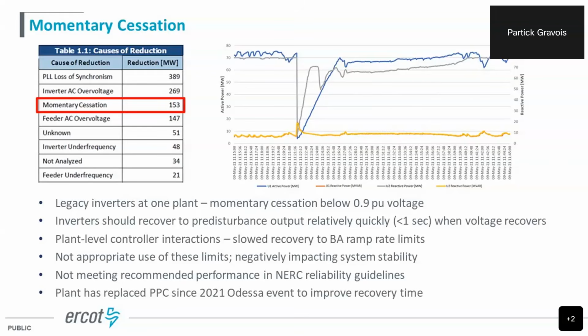So again, this being an older plant, I think it just really wasn't looked at closely when this plant was being commissioned. So what we did with this plant, even with the momentary cessation, we would expect them to be able to come back and recover to their pre-disturbance output within under a second, really. And that's not what we saw from this plant. We saw this was 2 units in one facility. One of them, you see the ramp rates in the top right, took about 1.5 minutes to come back. The other took closer to 5 minutes. So they really couldn't explain why these 2 units took different time periods to come back. They thought they were set to the same ramp rates.